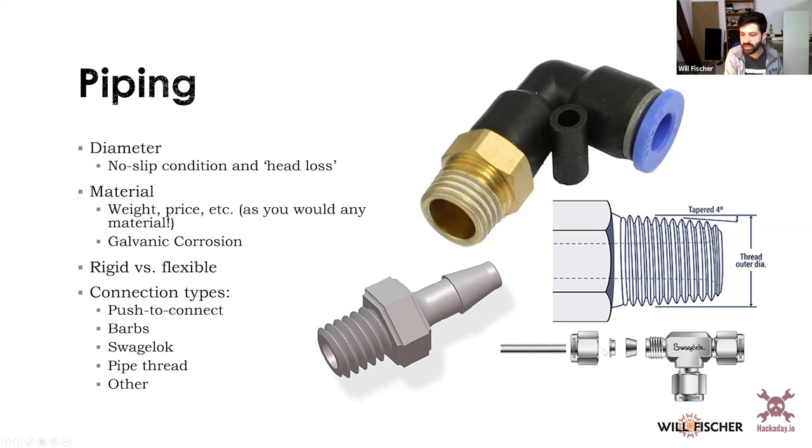And what this does is it has a taper that fits into a socket. And then when the tube is cranked down against it, it deforms a ferrule into the tube and into the taper simultaneously. And these systems can handle, gosh, a ton of pressure, hundreds of bar when they're properly assembled. And they're really nice because they're pretty easy to take apart as well. They don't ever hold quite as much pressure after the first time, but you can still get very high pressures and have something that comes apart easily and goes back together.